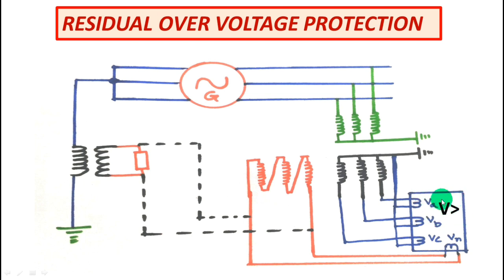I have written here V greater than. That means if you see that anywhere the relay is written as V greater than, you have to understand that that is an over voltage type relay. So this relay detects earth fault by over voltage.